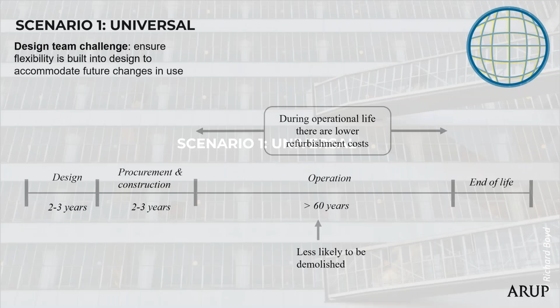This scenario really comes into play during the operational period - the building can be straightforwardly and affordably reconfigured in the event of a change of use. In the case of the UCL Marshgate building, we found the most onerous condition was for 40% of the floor area to be dedicated to high spec labs. The original brief already had 25% for labs, so there wasn't a huge change in design to allow for that potential 40%. The greatest changes were actually seen by the electrical systems, including increasing the electrical capacity by around 15% to meet that future demand.